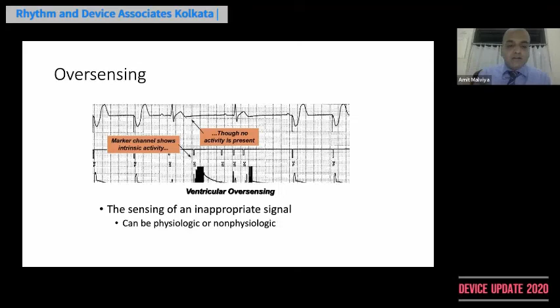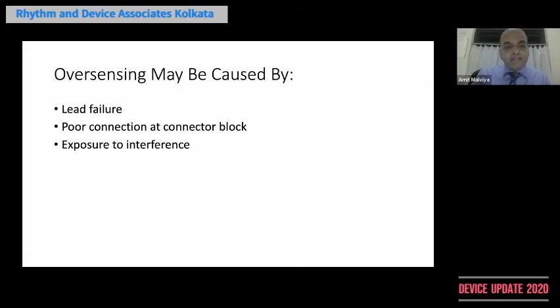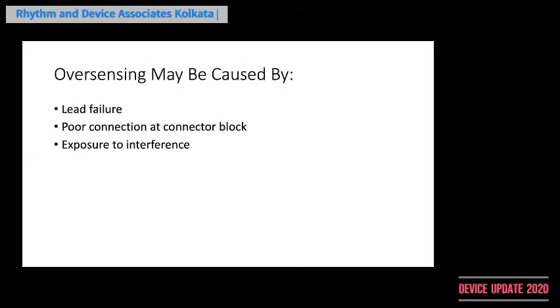Now this oversensing can be physiologic or non-physiologic. Physiologic, as I said before, means conditions related to the pathology of the heart. Non-physiologic means external interferences. Other important causes of oversensing are lead failure, poor connection at the connector block, and exposure to interference. Now this interference can be external or internal. External interference means external electromagnetic radio waves, or internal interference like enhanced myopotentials.